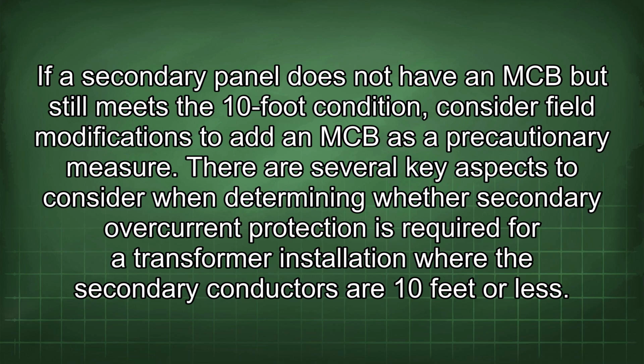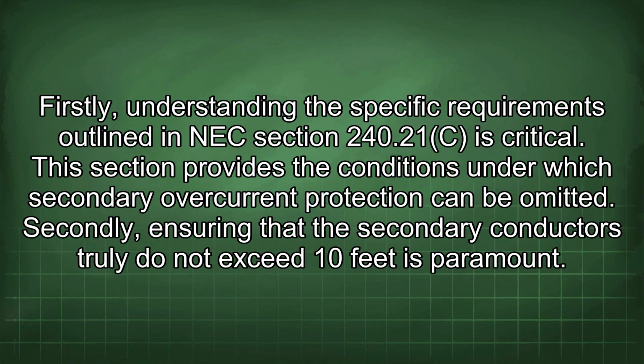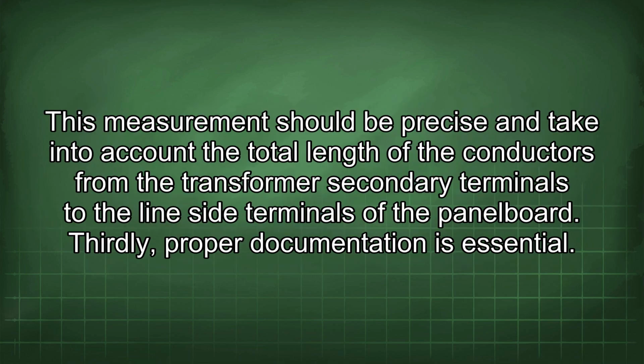There are several key aspects to consider when determining whether secondary overcurrent protection is required for a transformer installation where the secondary conductors are 10 feet or less. Firstly, understanding the specific requirements outlined in NEC section 240.21(c) is critical. This section provides the conditions under which secondary overcurrent protection can be omitted. Secondly, ensuring that the secondary conductors truly do not exceed 10 feet is paramount. This measurement should be precise and take into account the total length of the conductors from the transformer secondary terminals to the line side terminals of the panel board.